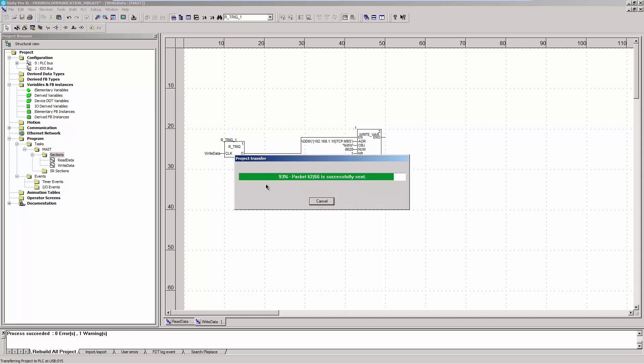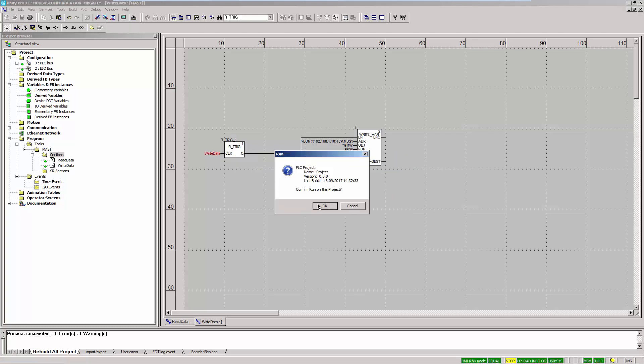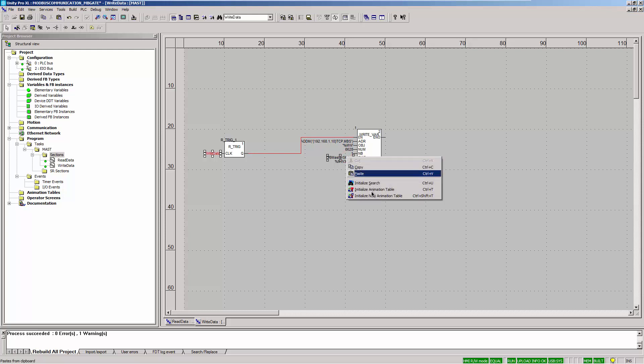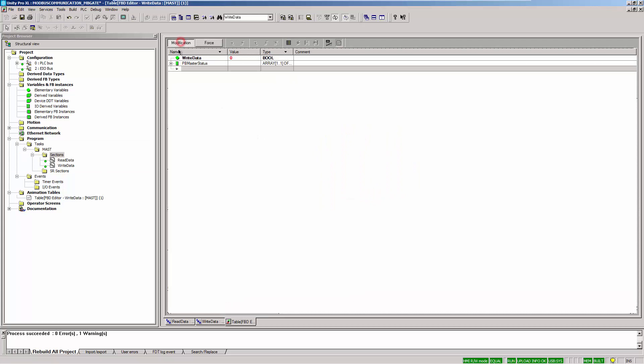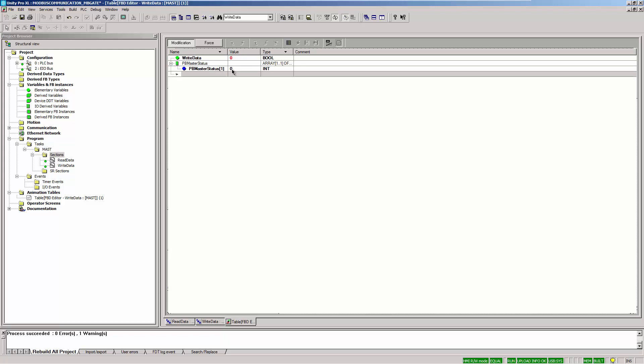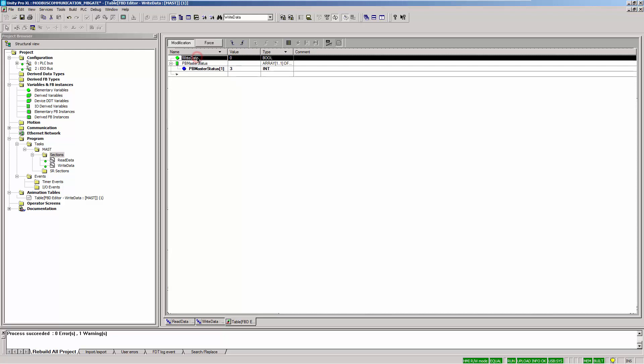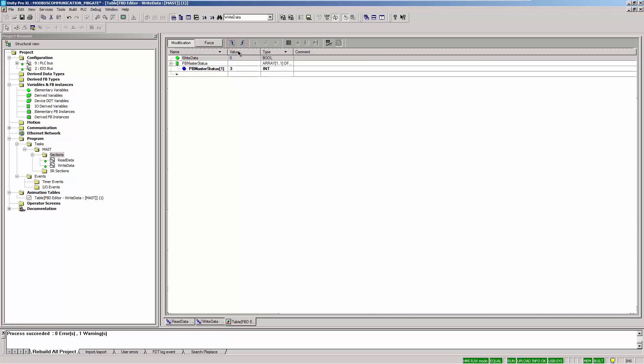In the following, we will write the PB Master status and read the status information and input data. Select the parameter to be written and the input variable of the R_TRIG block. Initialize a new animation table by right-clicking on one of the two selected parameters and selecting the corresponding option in the context menu. Change the value of the variable to be written to 3 — this corresponds to run mode. The writing is executed as soon as the input variable is set to 1.